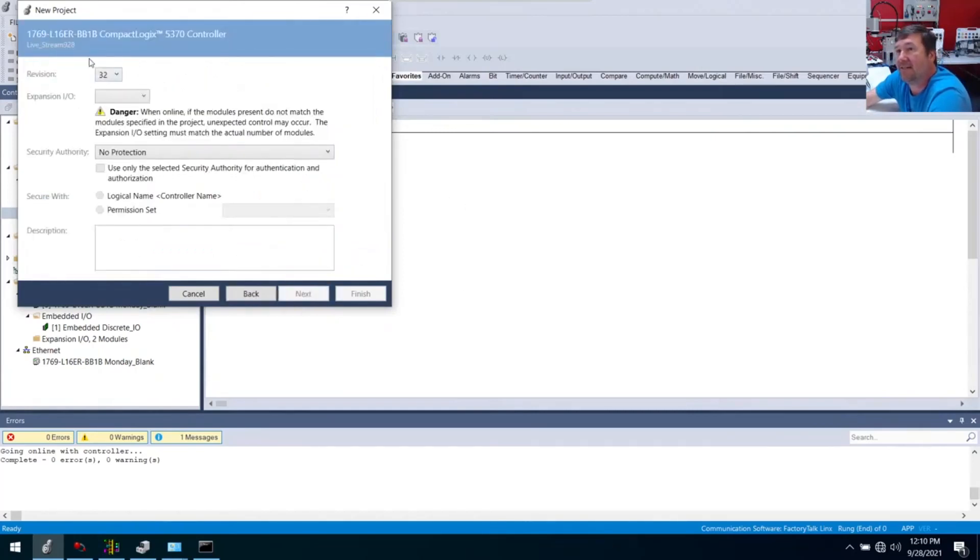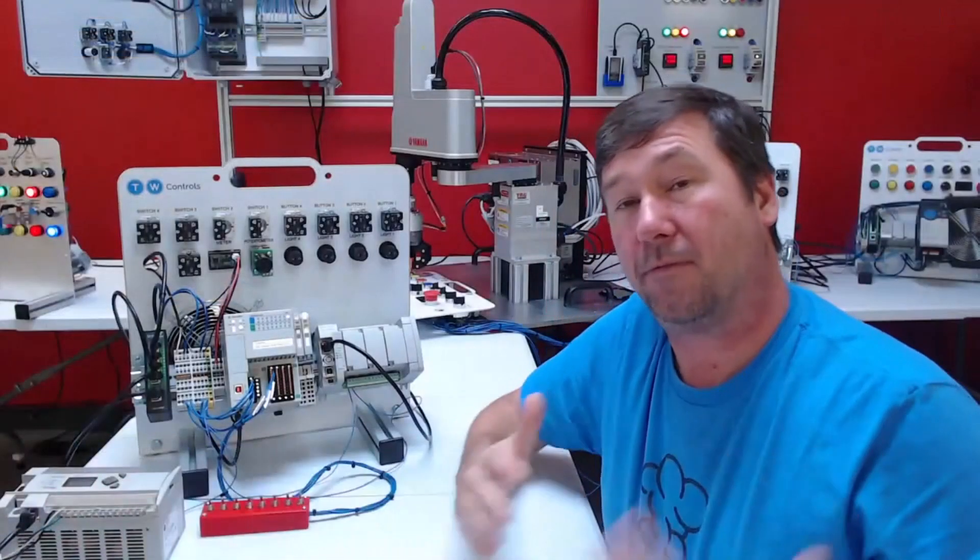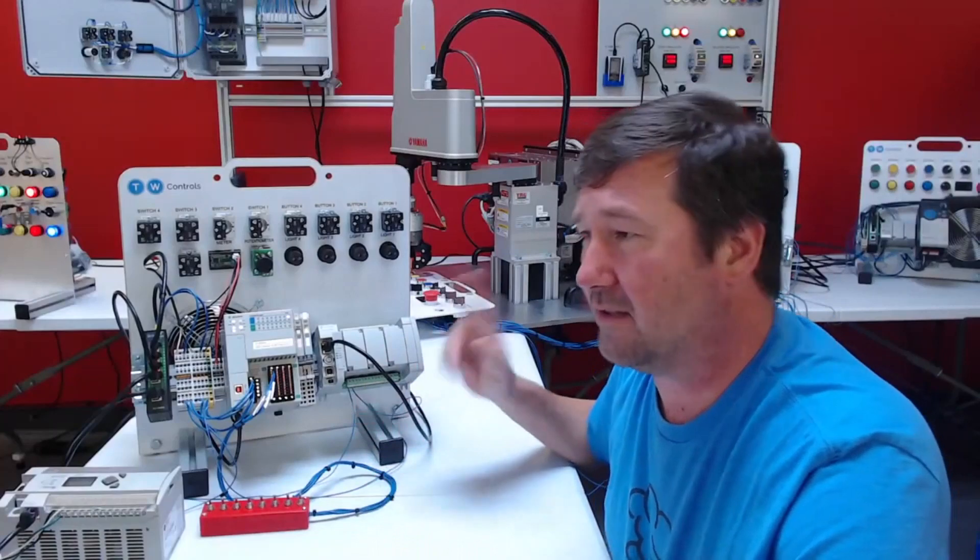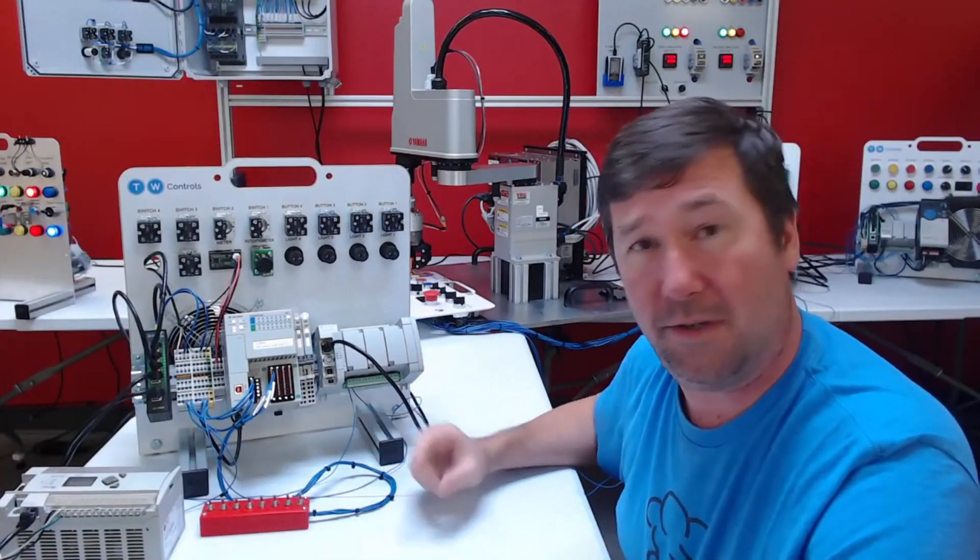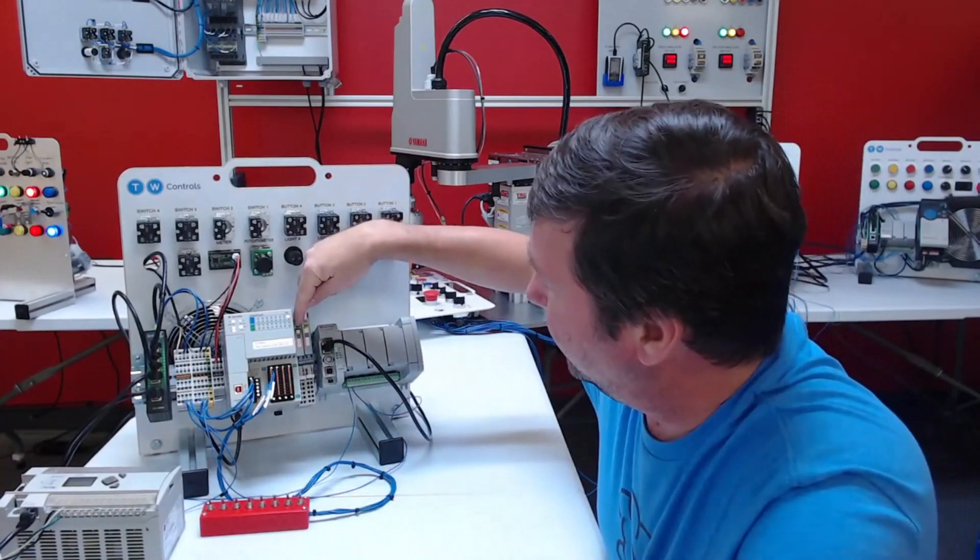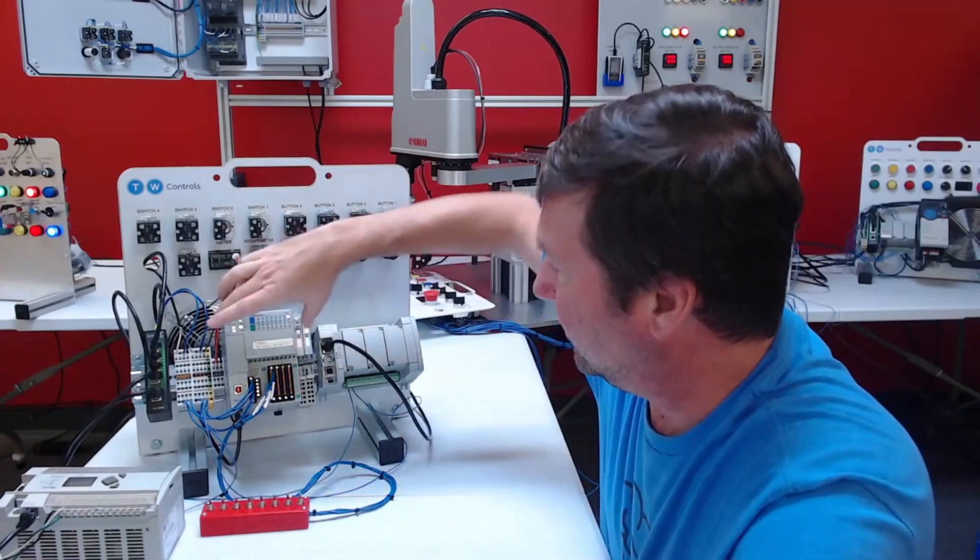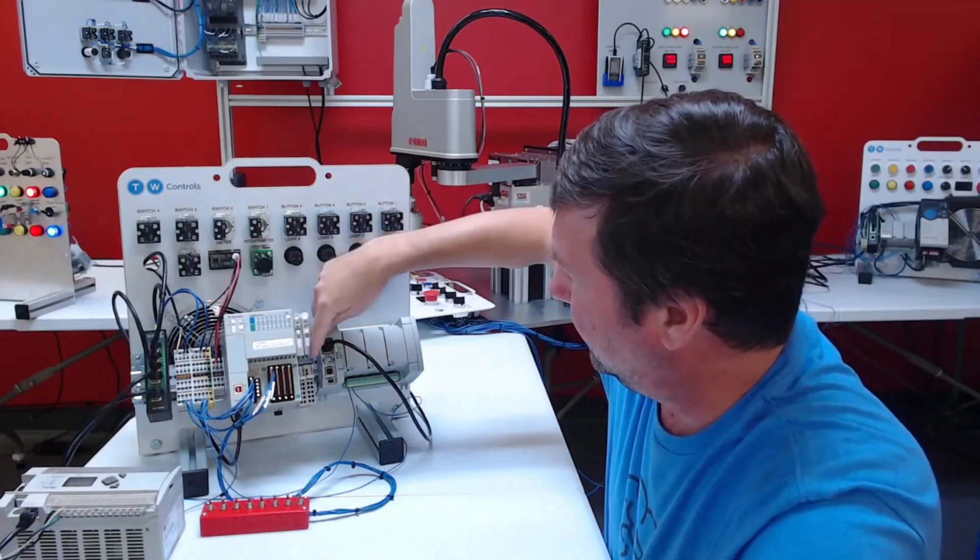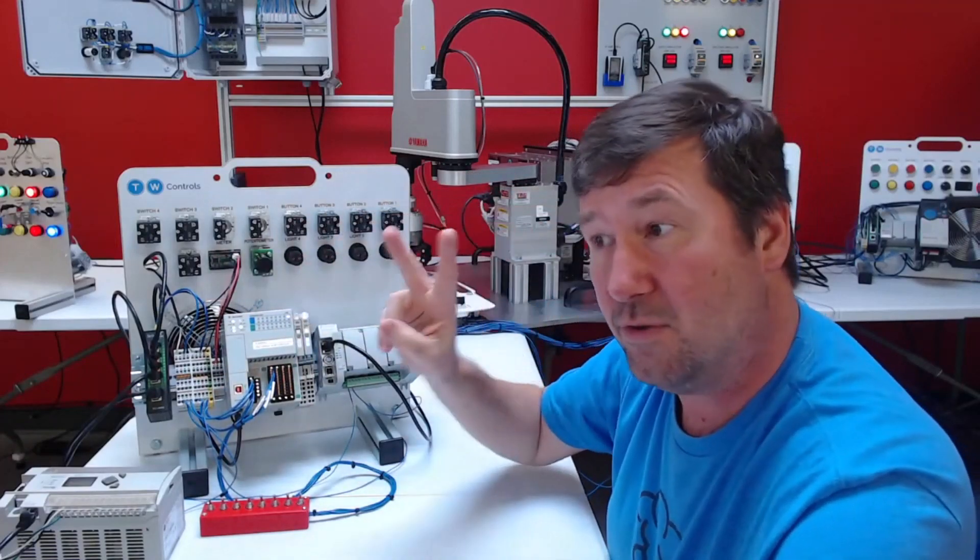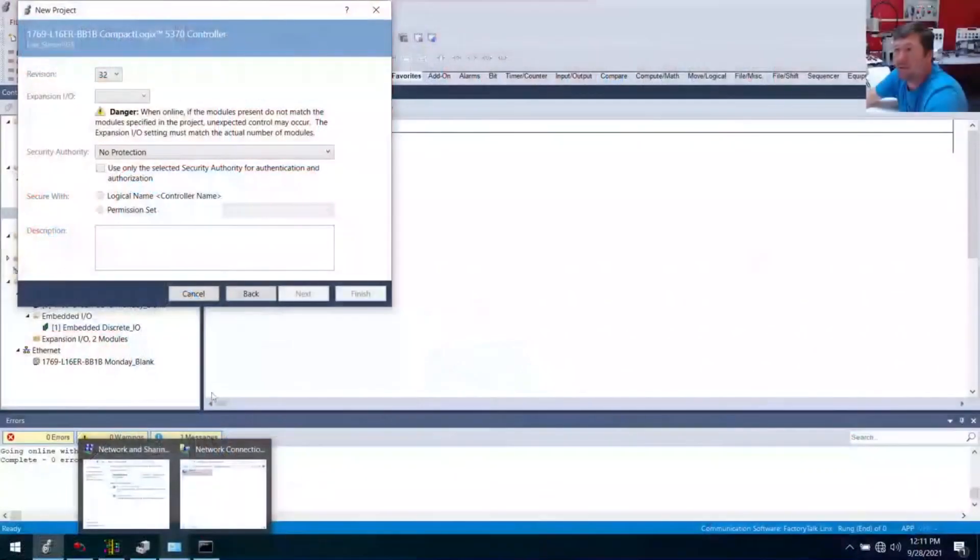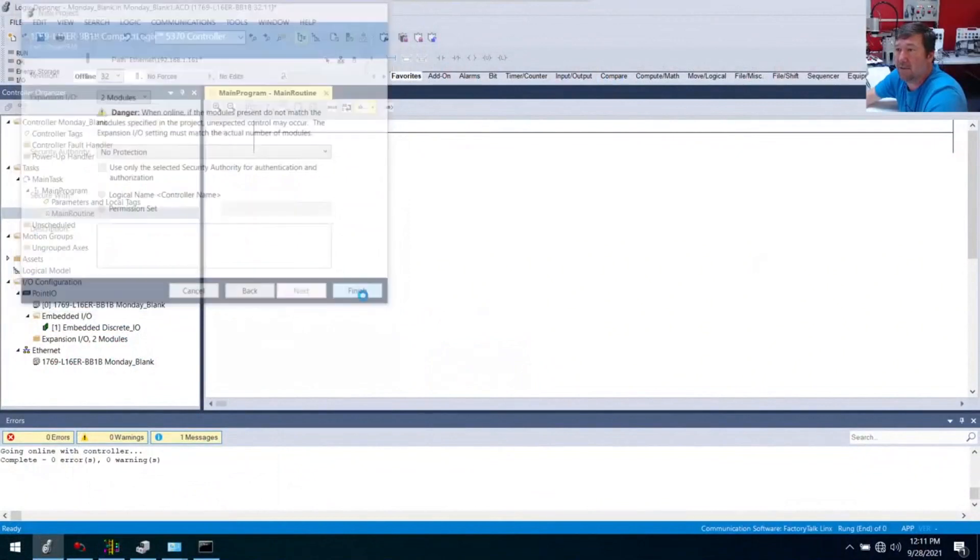For the L16 or the point I/O ones, you actually have to tell it how much expansion I/O it has, and it will fault the controller if you don't. That is the number of modules to the right of the PLC. This is our base PLC, and then we have this and this, so that is two expansion modules. We're going to put in a two there and hit the finish button.